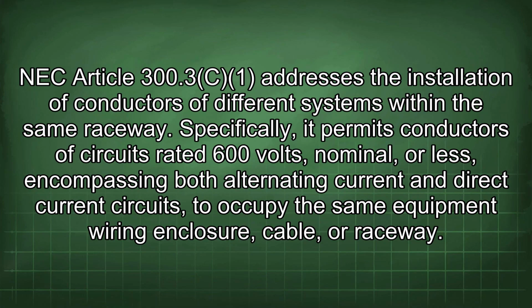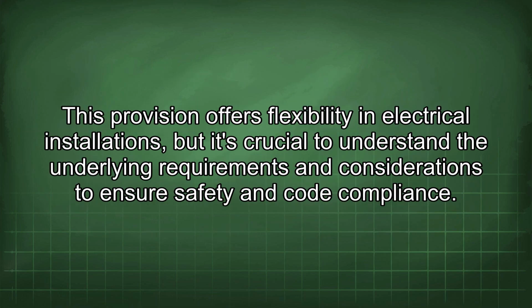NEC Article 300.3(C) addresses the installation of conductors of different systems within the same raceway. Specifically, it permits conductors of circuits rated 600 volts, nominal or less, encompassing both alternating current and direct current circuits, to occupy the same equipment wiring enclosure, cable, or raceway.